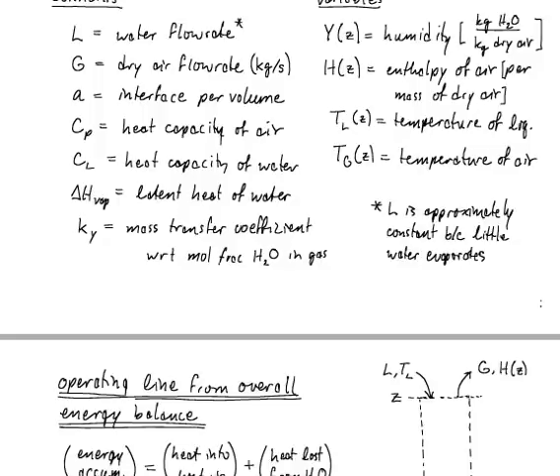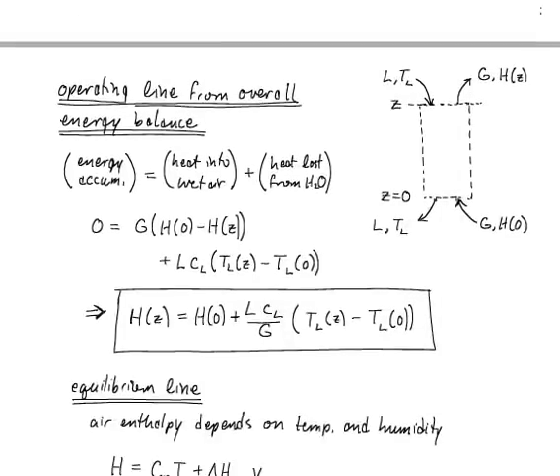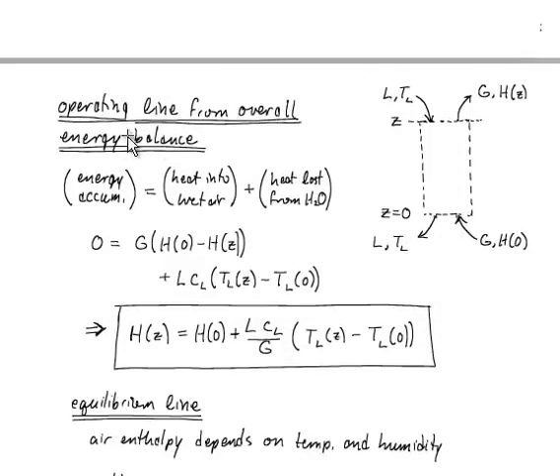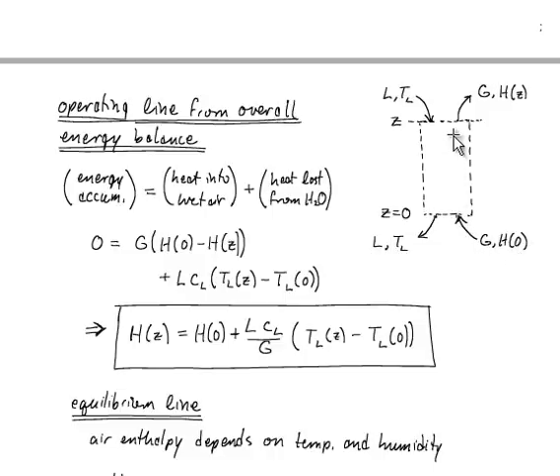This description of a cooling tower involves a few different balance equations. We start with an overall energy balance to obtain what we call an operating line. The control volume encloses the entire tower, with a hot liquid stream entering the top and cool liquid leaving the bottom, and dry air entering the bottom and moist air leaving the top. At steady state, energy accumulated in the control volume is zero.